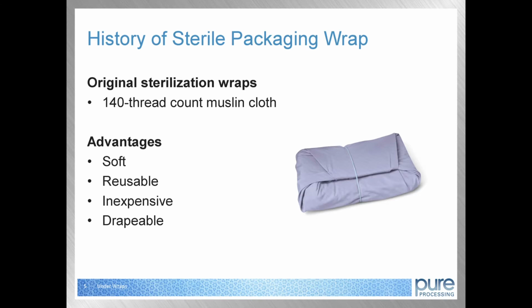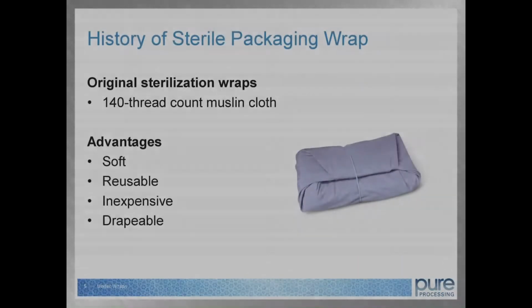About 80 years ago is when the first wrap came out for wrapping sterilization pans. It was a 140 thread count muslin cloth. It did have some advantages. One of the advantages was it was soft, it was reusable, inexpensive, and drapable, which is really nice. It was really easy for you to drape a pan, wrap a pan, and do whatever necessary to make sure that that pan was covered completely for sterilization. It was also really soft and easy to use, so it was really good when you were removing it from the shelves, putting it on the case carts and all that. And it was an inexpensive cloth, and it didn't cost much to be able to wrap a pan. So those are some of the advantages of it when they first started 80 years ago.